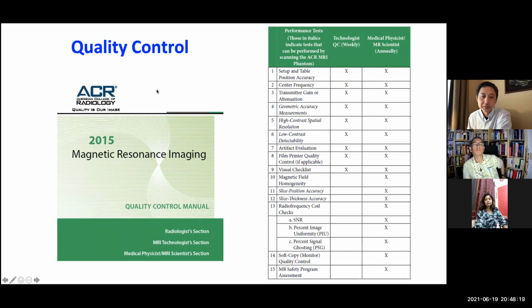So far I have mentioned acceptance testing. How about quality control? Most sites in the US follow the ACR guidance, and ACR requires technologists to perform weekly testing, okay? Again, apologies for the small font, but I will read through. Weekly, technologists need to perform setup and table position accuracy, central frequency monitoring, monitoring transmitter gain and attenuation, measuring geometric accuracy, high contrast spatial resolution, low contrast detectability, and artifact evaluation. If they are still printing film, they need to do film printer QC and a visual checklist.